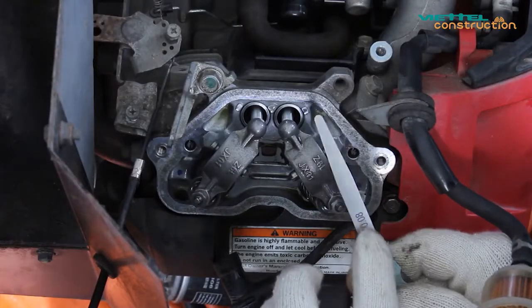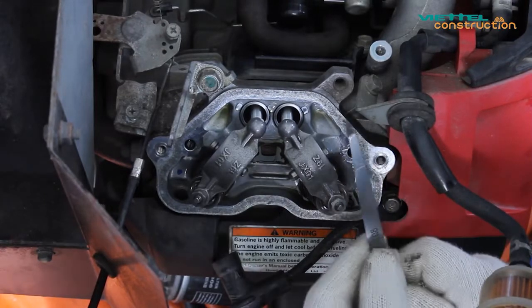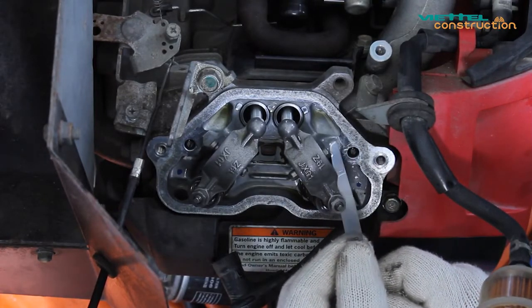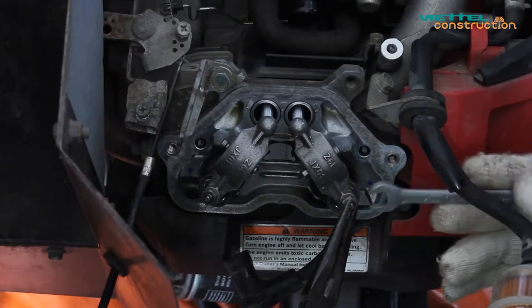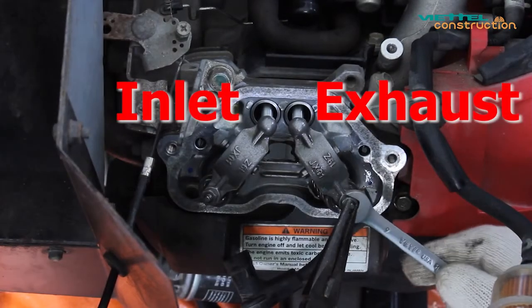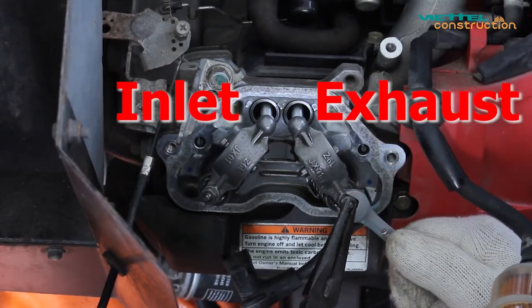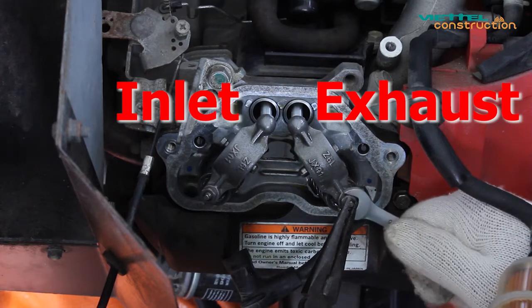Use feeler gauges to check and align the valves, so that the suction side has a clearance of 0.08 mm. The discharge side has a clearance of 0.1 mm. Note, the valve near the exhaust is the exhaust valve.